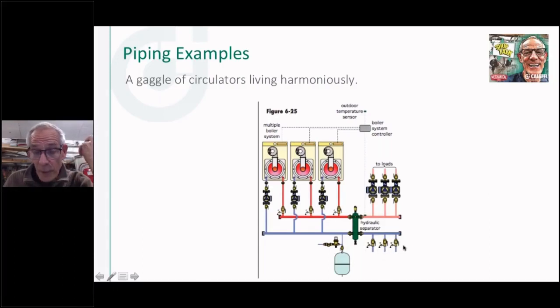And a great spot, by the way, to put a purge type of valve. I mean, pick a brand. There's a couple of them out there, but Webstone is one of the big ones. So if I put a ball valve there with a purge cock, now I can purge out every one of these lines or loops or zones, whatever they are, individually. And then once I do that, I can just turn this thing on. There's usually air vents built into the boiler that when I fill them, I'm going to vent air out here, purge out my loops, turn this on, and this thing is going to take off just like that.